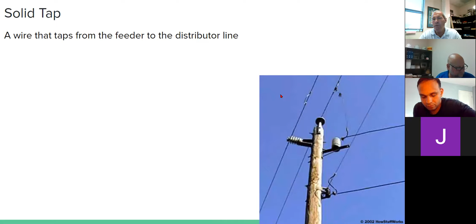Got it, solid tap. Now a solid tap is coming off the feeder line, but I don't have a fuse. It's an unprotected, non-fused line from the tap line off the feeder - a wire that taps from the feeder to the distribution line, with no fuse.